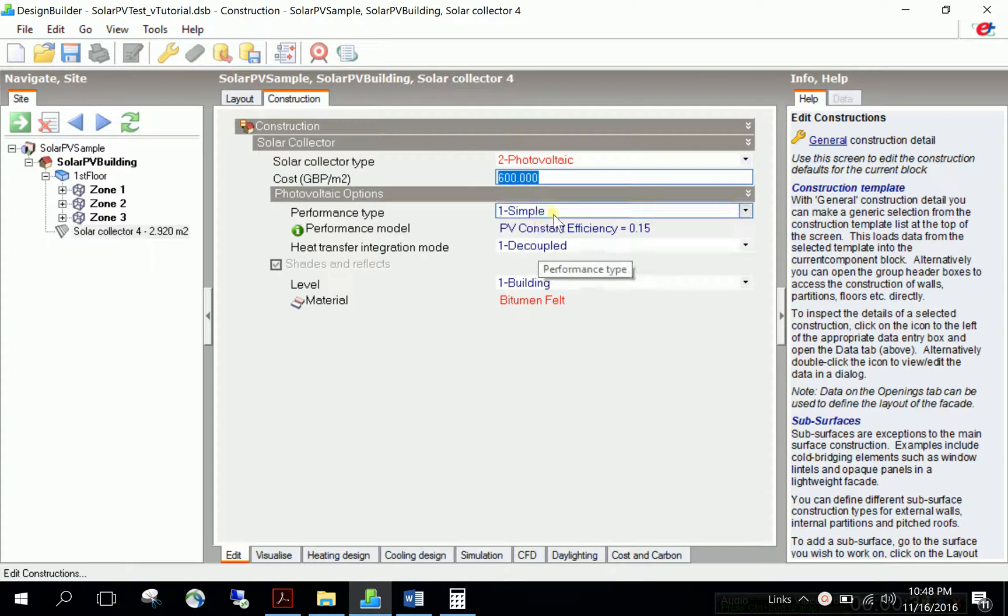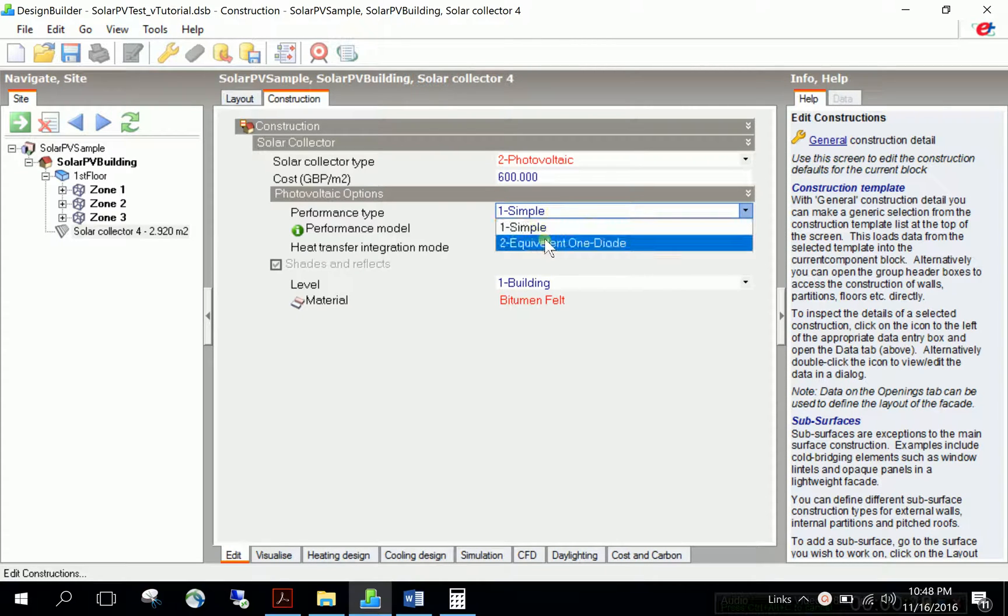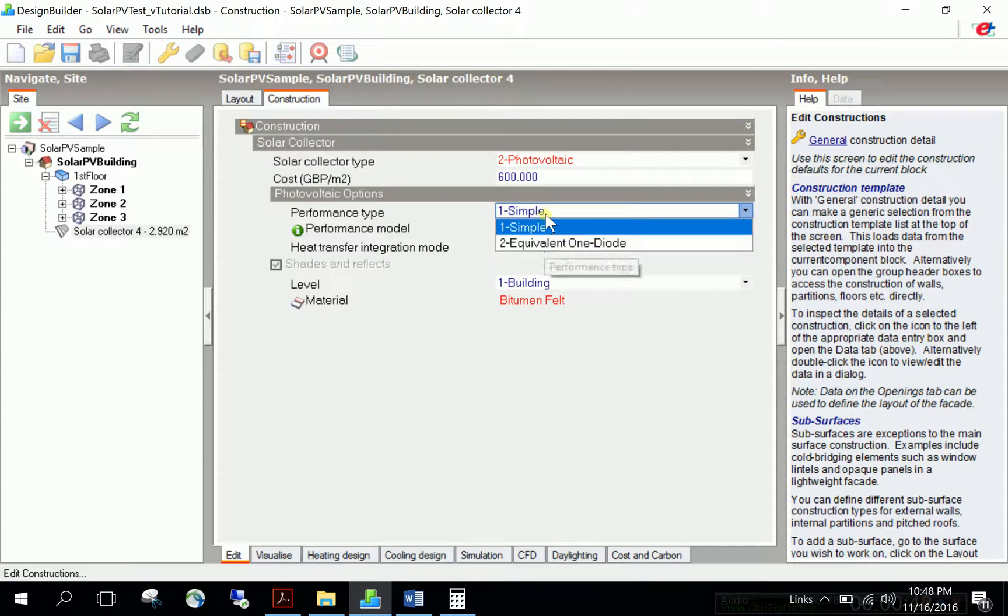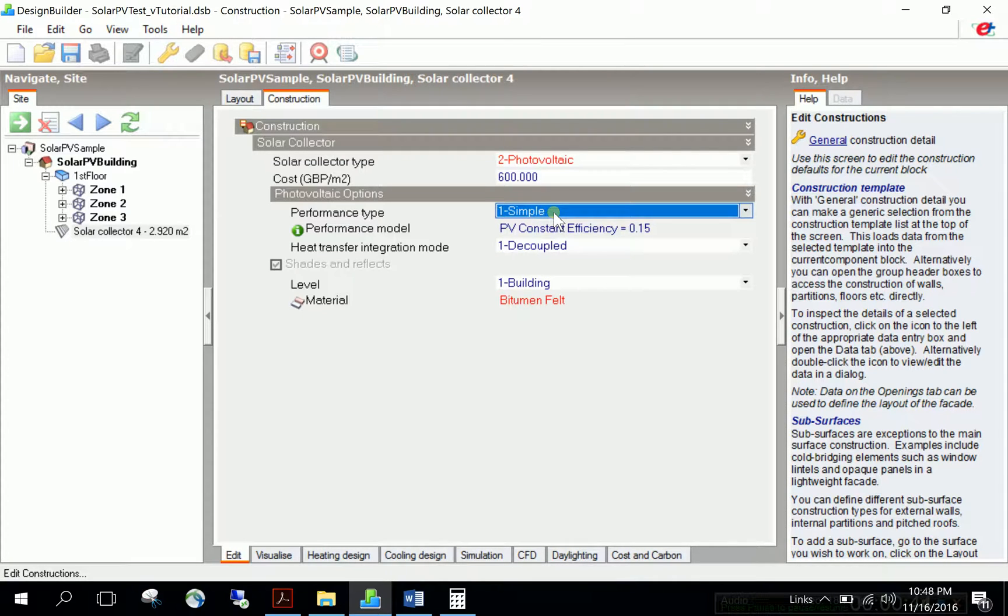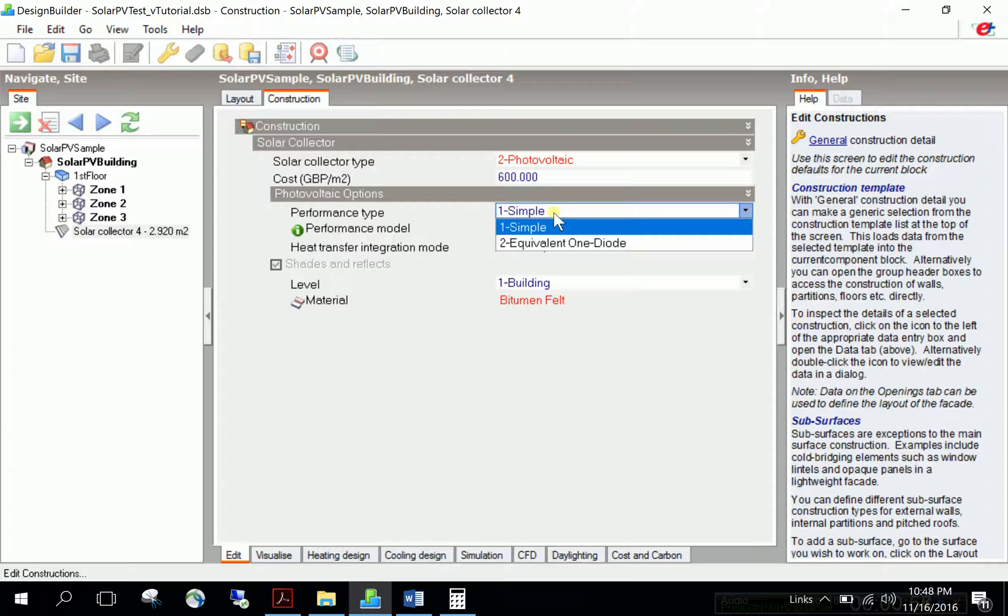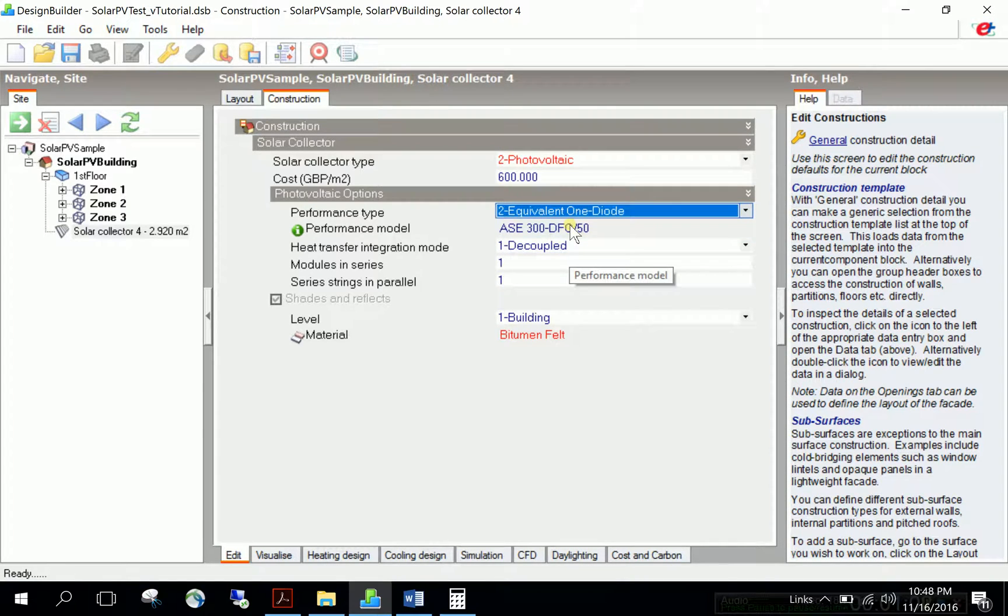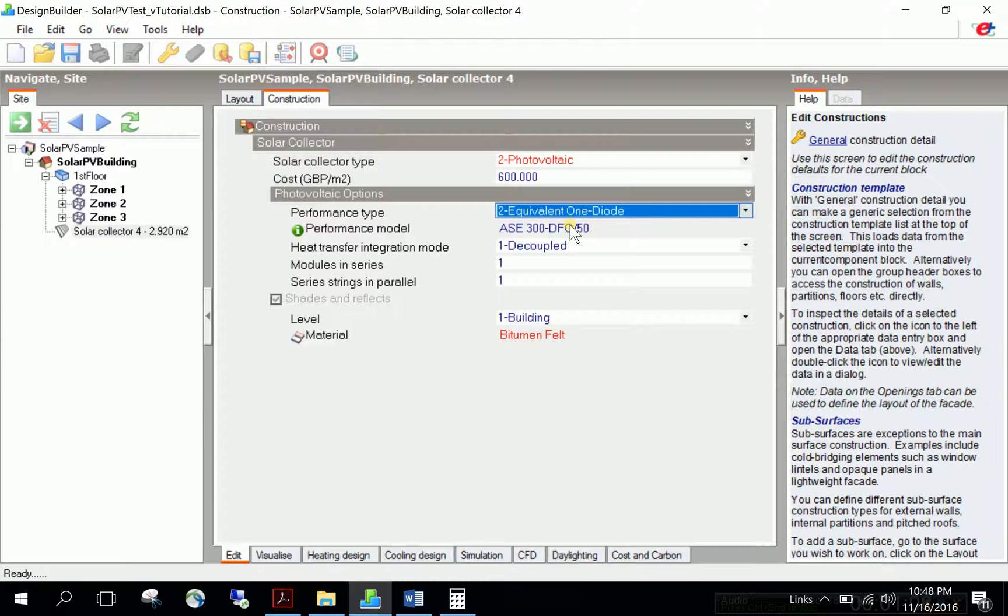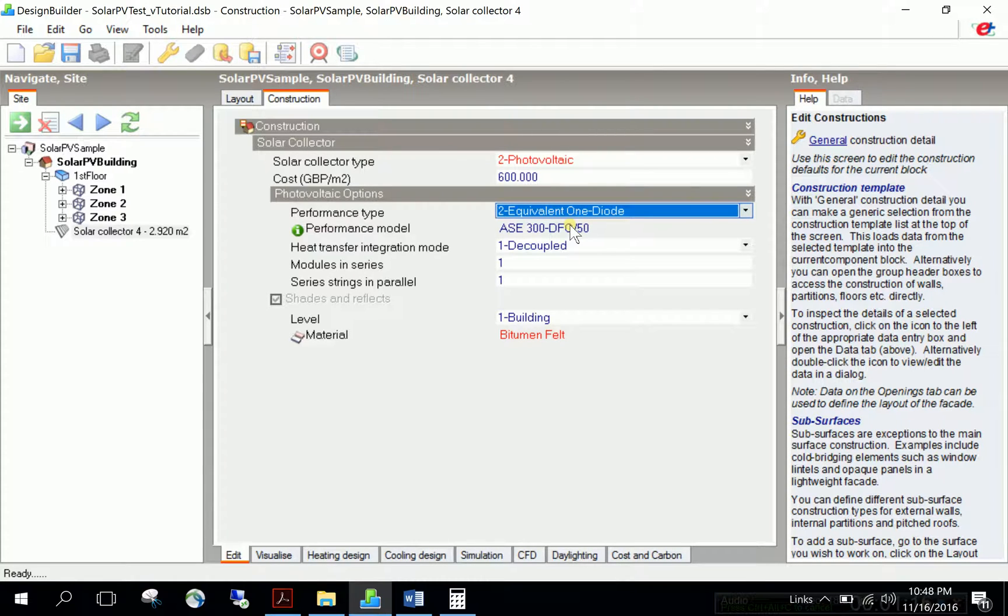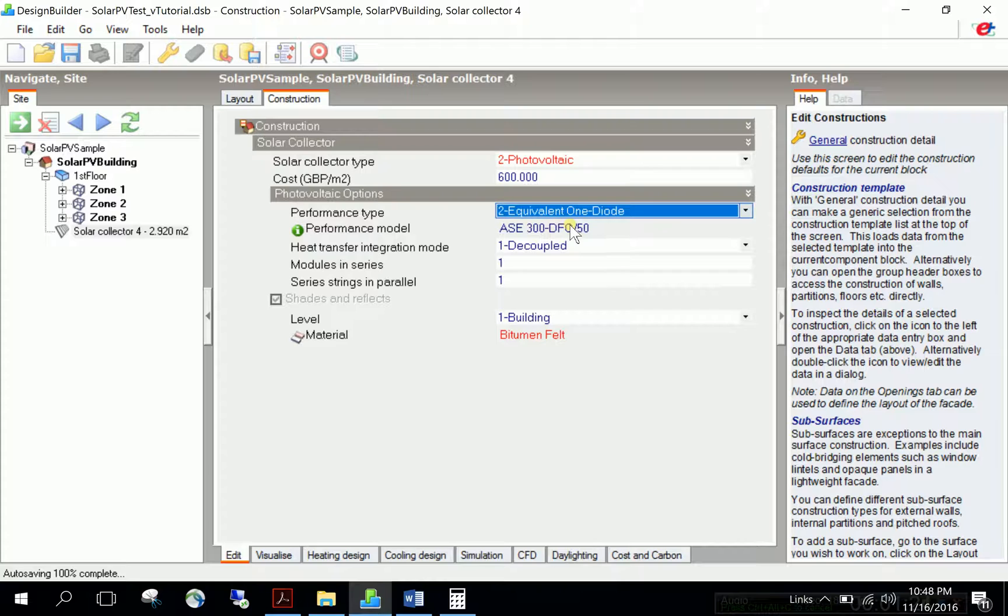For performance type, there are two choices: simple and equivalent one diode. The simple one uses a constant solar radiation conversion efficiency, which can be fixed or schedule-based, but doesn't come from an electrical performance model. Equivalent one diode is more responsive to environmental conditions, using a four parameter electrical analogy circuit model that characterizes PV module performance under different solar radiation levels, outdoor temperatures, and cell temperatures.